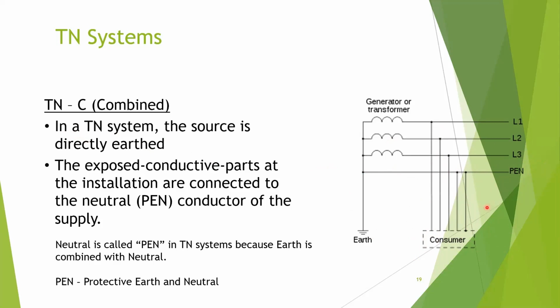So in the TT system we are getting a wire from here and connecting it directly to ground. So you are not utilizing neutral as your return conductor as an earthing conductor. But here we are using our neutral conductor as an earthing conductor in the TNC system. That is why it is called combined. When it is a combined system, it is called PEN, protective earth and neutral. So that is how a TN system is wired.